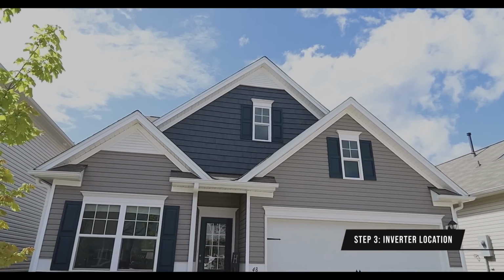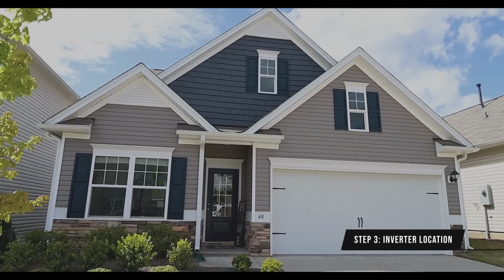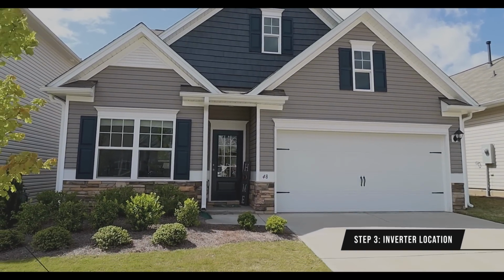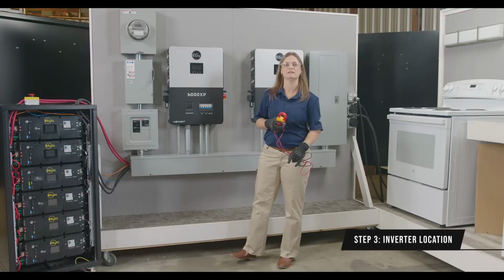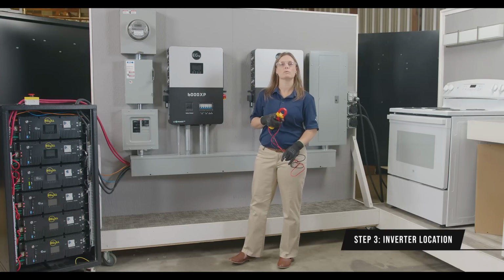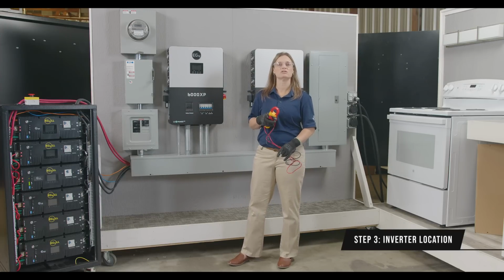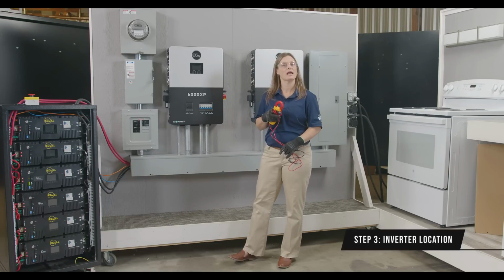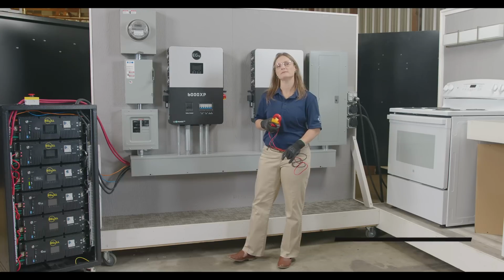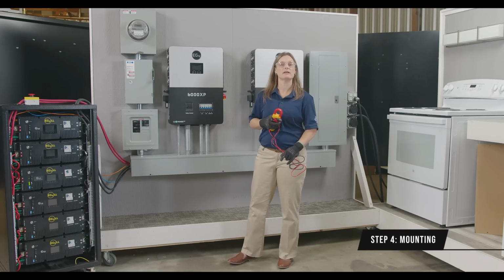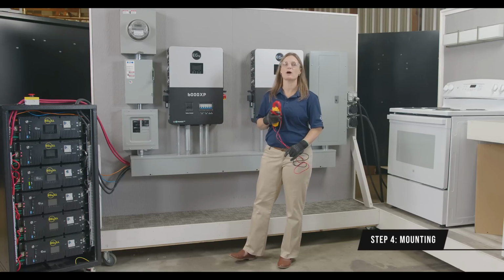Let's find the perfect spot for your inverter. Find a location that has good ventilation, providing adequate heat dissipation. Designed with an IP20 rating for indoor use, ensure that the unit is positioned away from direct exposure to sunlight and areas where snow can accumulate. Once you've settled on the right place, it's time to get that inverter up on the wall. Keep in mind, it needs to be upright and sturdy enough to support its 53-pound weight.